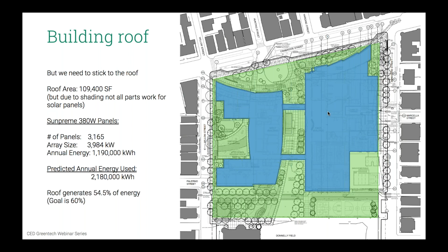Overall, the city decided they wanted to stick with solar panels only on the building form itself. We did our analysis of what we could fit, including all the required walkways for code, perimeter walkways, and roof hatch access. Most of the mechanical systems on this roof were put into sunken-in mechanical wells that we could put PV panels over top of. Through that analysis, we determined the roof itself could generate 54.5% of the energy, but our target was 60%.